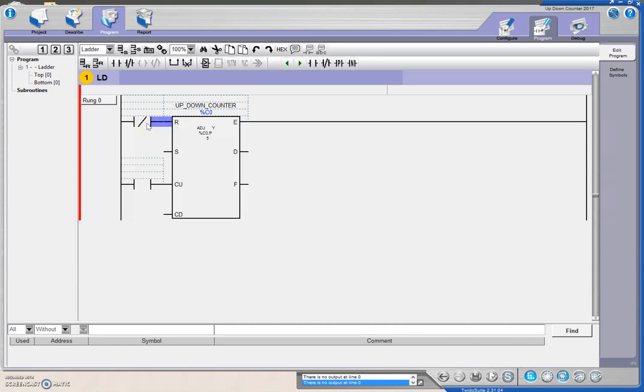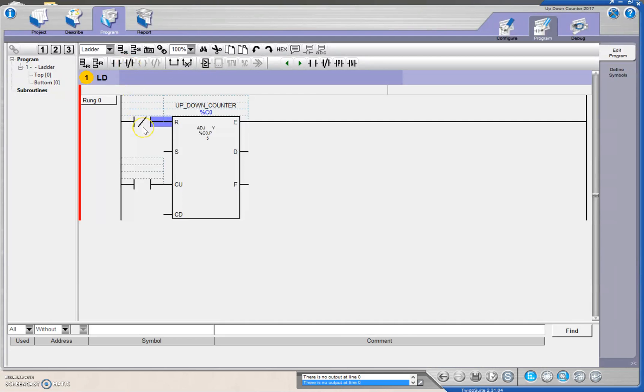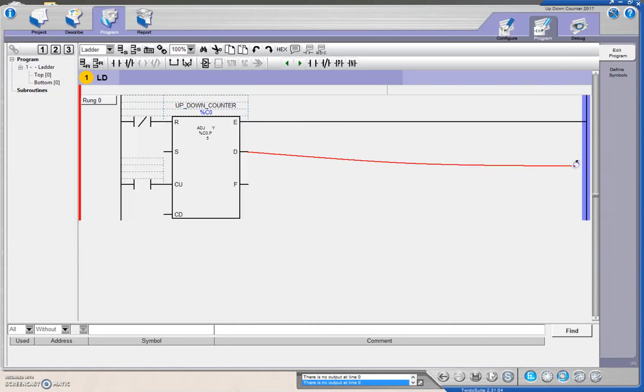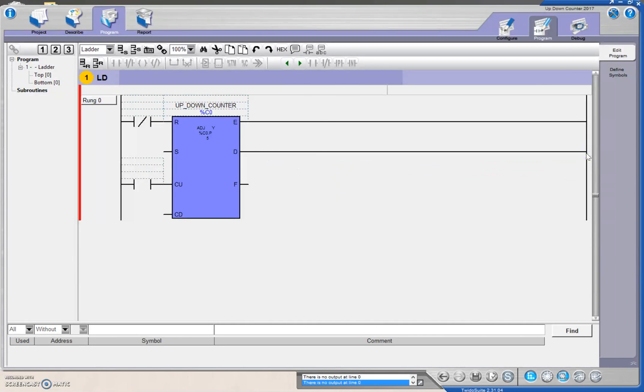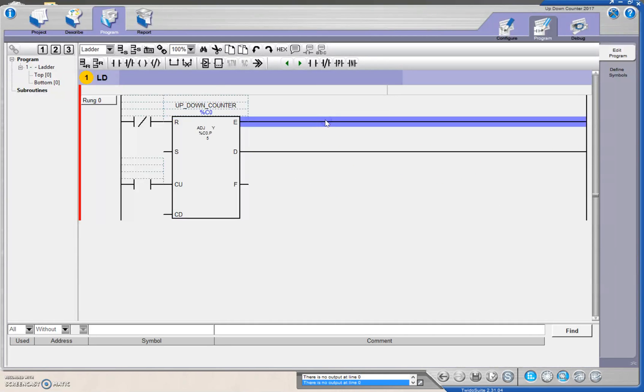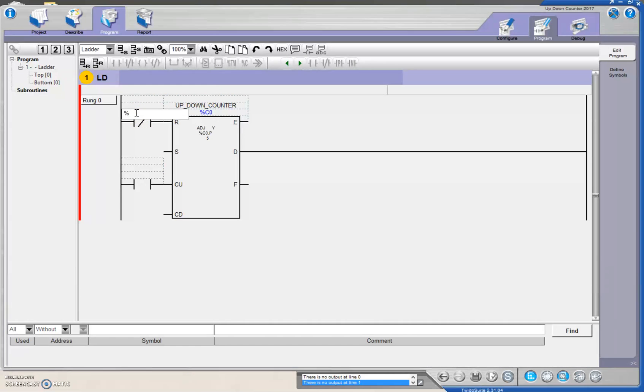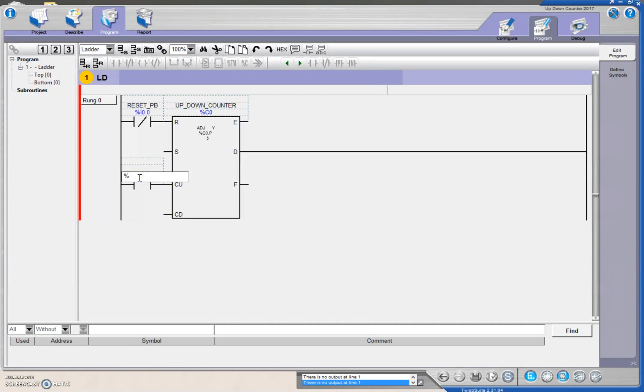If you're using a normally open contact, then you would use an examine if closed. I'm using a normally closed contact, so I'm going to examine when that guy opens and changes state. From there, I need the done bit, so I'm going to grab this guy, bring it across to this rung. I'm going to put in this as percent input 0.0 for the reset. This guy for my count up was percent input 0.1.